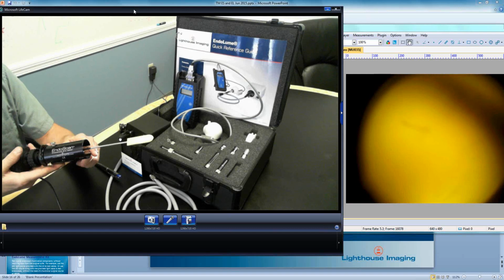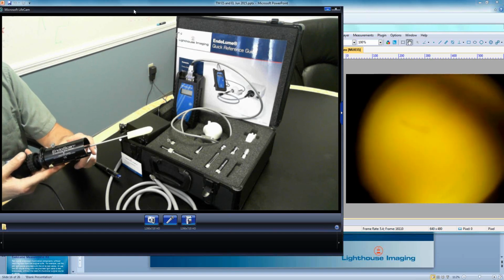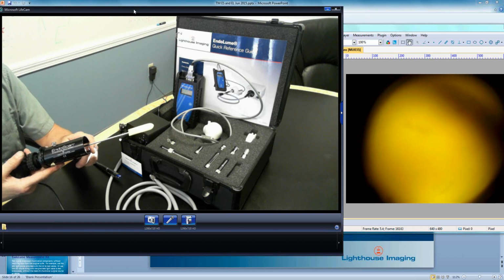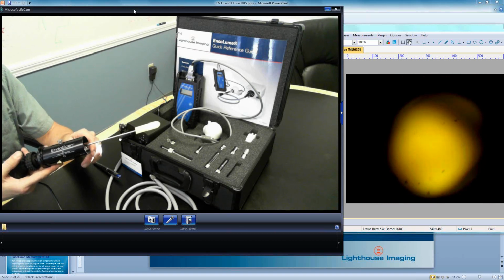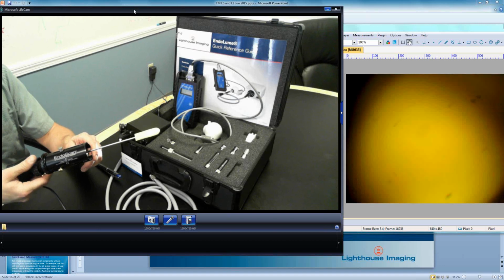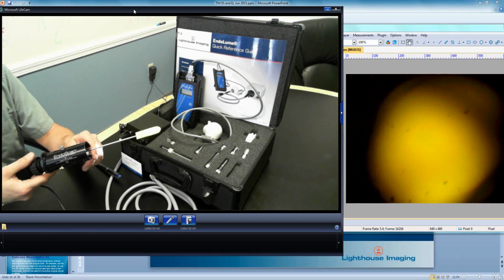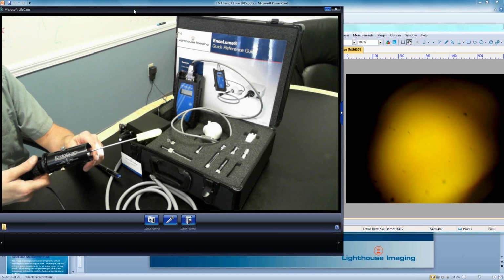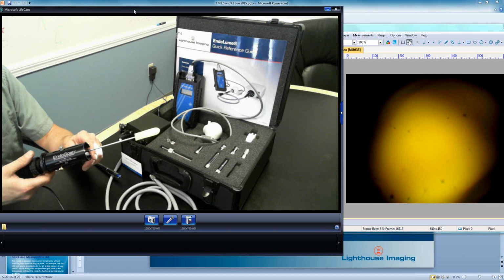So when we attach it to the EndoScan here, we'll see, if we now watch the yellow tinted image, as I slide the EndoScan in and out, we see different features come into focus. So I'm going to zoom a little bit here, and we'll see that somewhere in this endoscope, we can see a little bit of debris on one of the surfaces. So there's a few small particles, but it's not terrible. And this is debris, not moisture intrusion. We can see that they're all small opaque components. And as I mentioned, this would not in any way be considered severe debris. So this is just a little bit of minor debris.